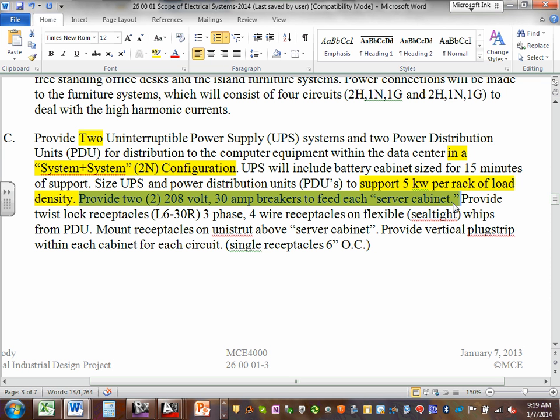Seems kind of stupid. So there's going to be some twist lock receptacles. There's going to be 2 at each server cabinet, and one is going to be to UPS A and one is going to be to UPS B, and 2 plugs from the computer will plug into each one of those. It'll be a nice stream all the way down. So your server is powered with 208. Yep. Not 120 like your computer. You bring in 2 hots to your computer. Yep.